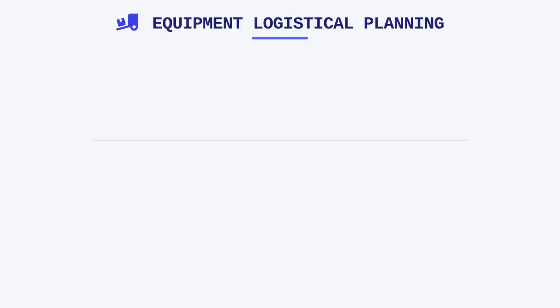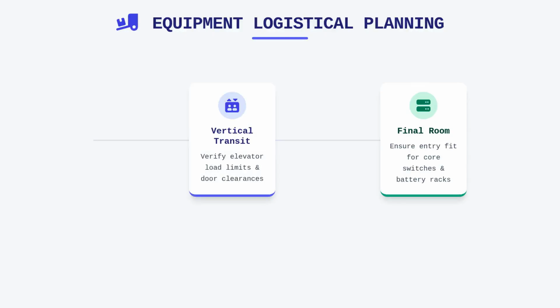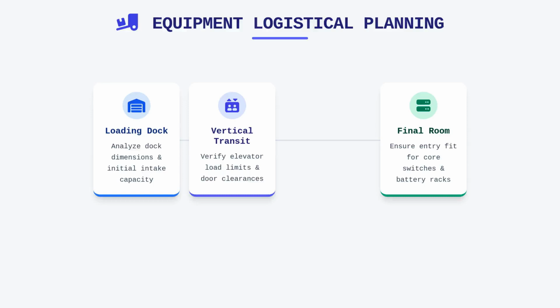A often overlooked but critical aspect of this discipline is the logistical pathway required for installing massive equipment. You must verify that your designated telecommunications rooms and hallways can accommodate the physical transit of heavy gear, such as high-density core switches or lead-acid battery cabinets. Before you finalize a floor plan, you need to verify elevator load capacities, analyze the dimensions of the loading dock, and calculate the turning radii throughout the building's corridors.